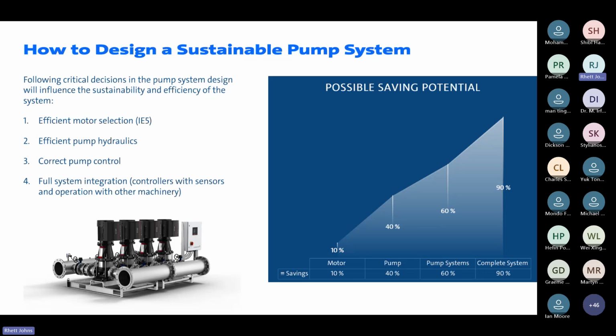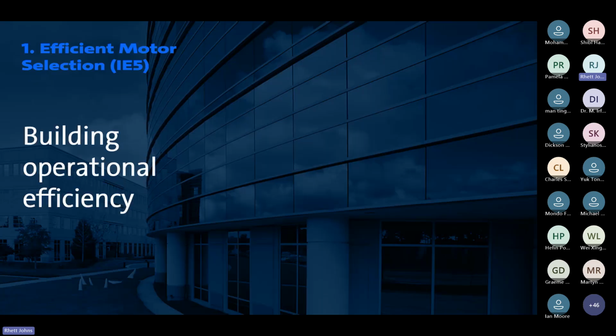That's not necessarily that we can reduce energy consumption by 90%, but if a system has got potential to reduce energy by 60, 70%, you would need to be looking at each of these individual components. So it all starts with the motor. Permanent magnet motors don't require induction to drive the motor and are able to maintain the highest part of the efficiency load in variable pump volume and systems.